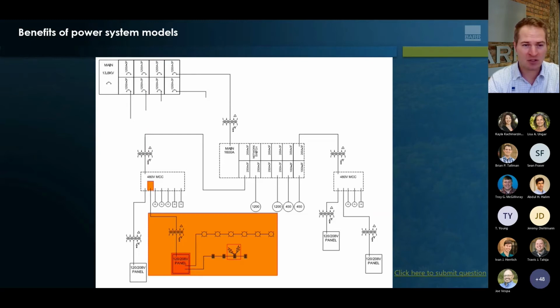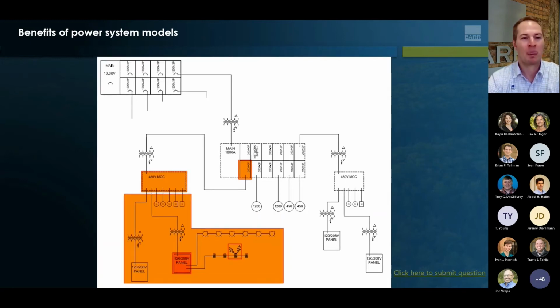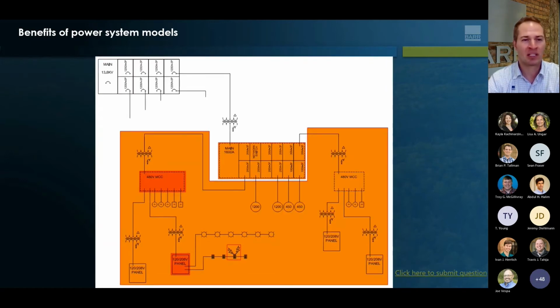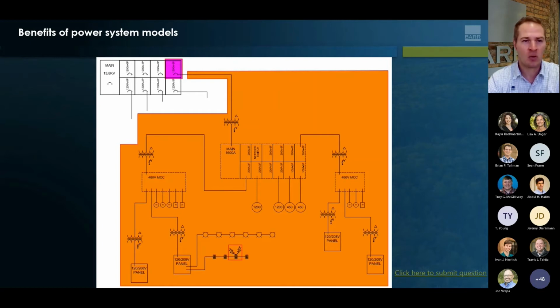Moving further upstream, if this panel didn't trip, you could trip a breaker here at the 480 volt MCC, and this whole leg goes without power. I'm sure you know where this is going. The system was not coordinated properly, and the trip actually occurred all the way up here at the main substation, and the entire underground facility was without power. This was 25% of the site, and it resulted in miners being temporarily stranded underground and stuck in the shafts.